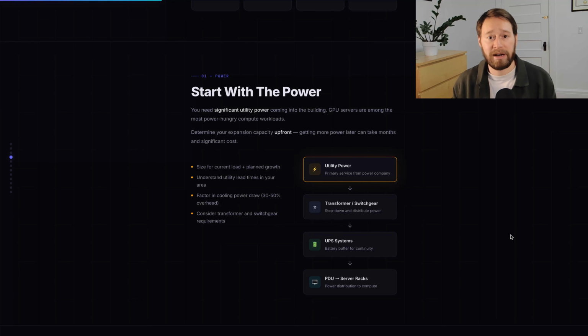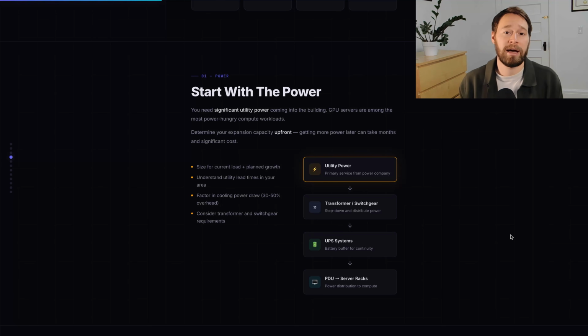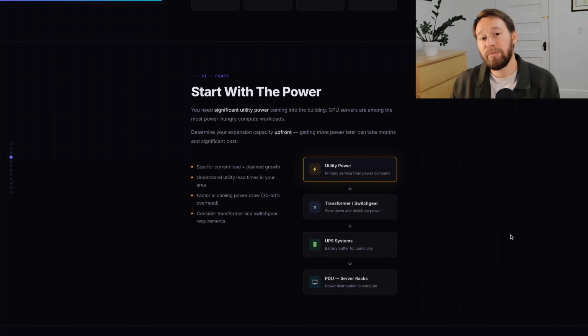What you're going to add in a data center is UPS systems, which are essentially big battery systems that receive the power at really high voltage and amperage. This could take your 480 volts coming off the transformer and put that into the batteries. Then on the output of that system, you're going to have clean, conditioned power that you can feed into the PDUs in your server racks.